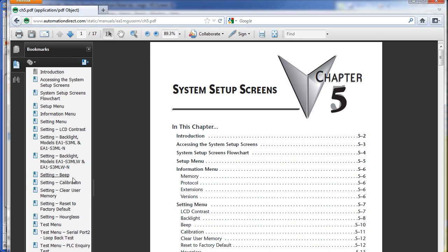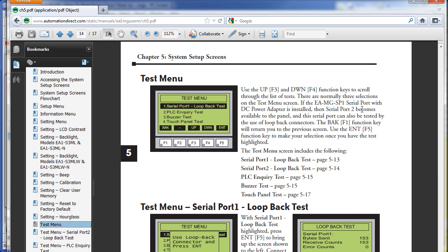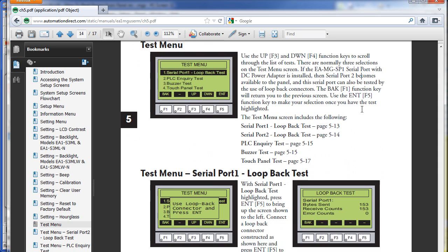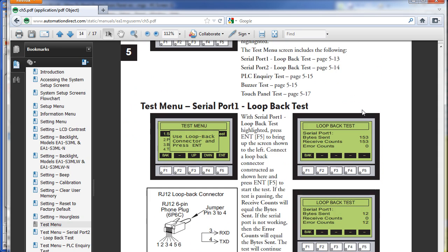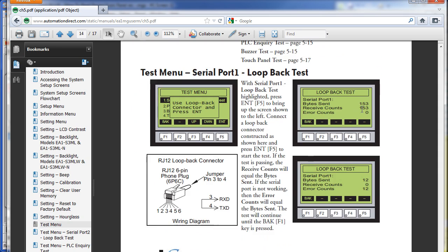In that section of the manual, there is actually a subparagraph on test menu for serial port loop back test. There is the test menu, serial port loop back test. So here is a picture of the cable that gets plugged in and what you have to do, that is just short pins 3 and 4 to make a loop back tester.